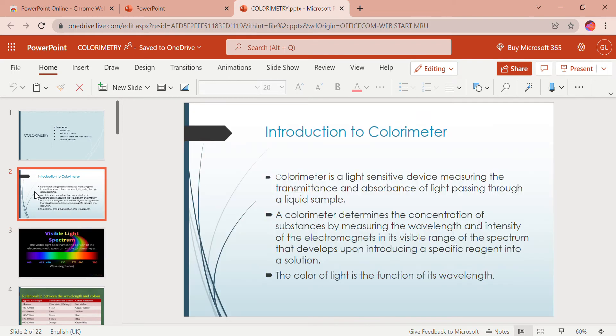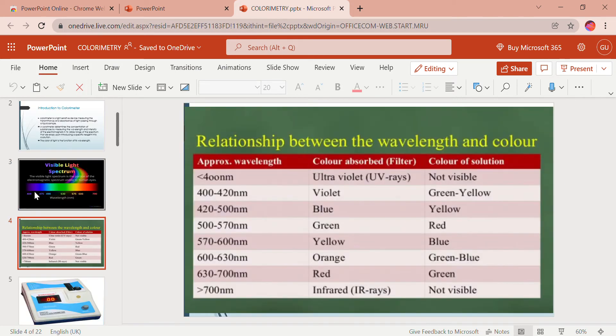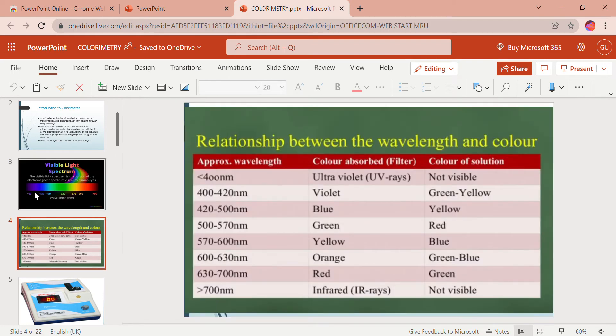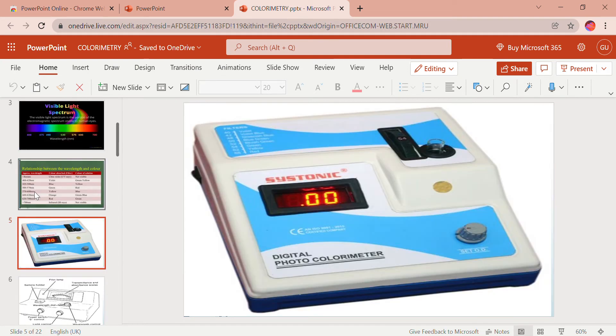The colorimeter determines the concentration of substances that absorb light in the visible region by measuring the intensity of light, which depends on color. The color of light is a function of its wavelength. For example, a wavelength of 400 to 420 nanometers corresponds to violet, and red has a wavelength of 630 to 700 nanometers. This is the visible light spectrum with wavelength in nanometers, and beyond it lie ultraviolet and infrared rays.